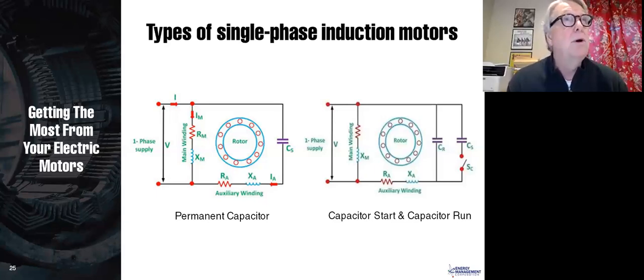You want to have a motor that has the appropriate starting torque, and the more starting torque it has, generally the lower efficiency and the lower power factor, and so on. There's lots and lots of judgment calls you make, and so they try to come up with a nice mix that gives you good power factor, good starting torque, good pull-up torque, good breakdown torque, good efficiency, and so on. But there are always trade-offs. Now, whether you need to increase the power factor of the motor depends on basically 2 things. Number one, if the motor is on a variable frequency drive, then you never need to increase the power factor of the motor, because the variable frequency drive does that for you. And even if the motor is 40% power factor, it will be 97, 98% power factor on your utility bus because of the variable frequency drive.